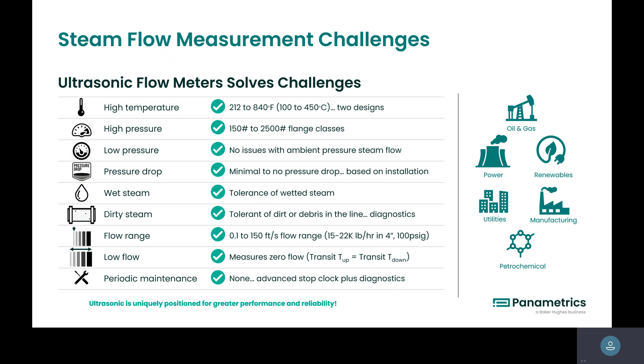Is ultrasonics new to steam? No. I think it's still surprising - I get a lot of questions about whether you can do steam measurement with ultrasonics. Yeah, we've been doing it for 20 years. It's not an issue measuring steam with ultrasonic flow measurement at all. I don't think it's one of the natural thoughts people have for steam measurements, but this was one of the papers presented back in 1999, I believe, and we released our first dedicated steam meters in 2001. So we've been measuring steam for a long time, and I'll go through some examples showing how we're using ultrasonic flow meters today to measure steam.